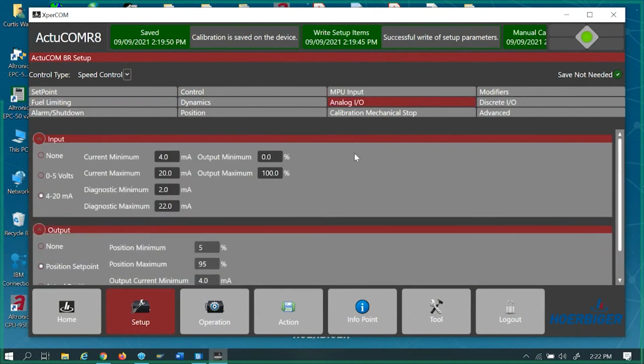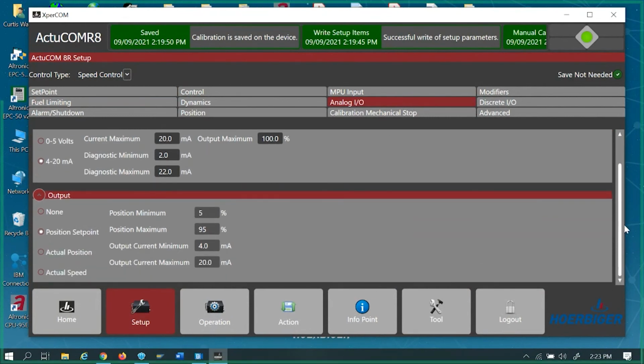Right. Your analog I/O, basically it's your 4 to 20. You can set your 4 milliamp at what percent on your movement, 20 the same. You can run a 0 to 5 if you like, or 4 to 20, or none at all. All of that comes with doing any kind of speed versus RPM, sending a 4 to 20 signal or 0 to 5 signal to modify the RPM going to the engine. Output, the same thing. You can do a position. If you want to feed back to maybe a PLC, they'll say a position feedback at 5% or 95% is open and shut, or the actual position off the 4 to 20, the same thing. Or you can just do actual speed. It says 0 to 400 on the output current of it. So anytime they're coming back to the control room, they want to see that speed, you could use this as a device to do that also.